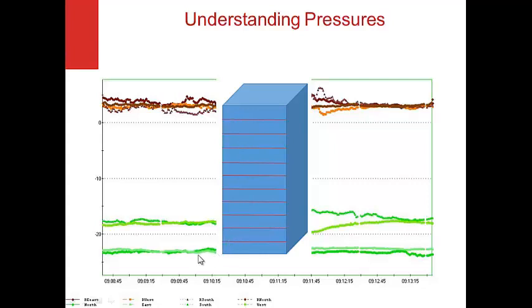If you ran a tube from the top floor to the bottom floor inside the building, you would measure zero pressure, because the weight of air in that tube is the same as the weight of air around it. If we measure pressure and ran the tube outside and brought the gauge up to the top, we would still be reading the pressure at the bottom — no matter where we go with that gauge in the building, if the tube exits at the bottom, we read the same pressure. To find the neutral pressure plane, we need to stick the tube out at that location.